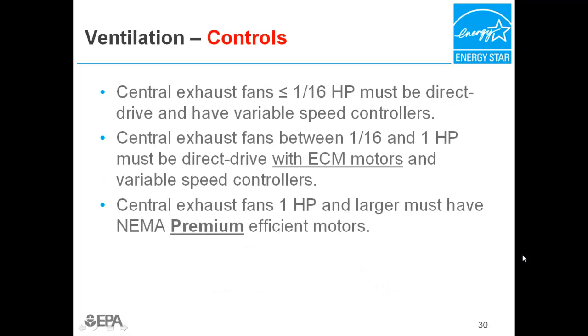All the ventilation control requirements on this slide are only applicable to projects in the prescriptive path. Central exhaust fans 1/16 horsepower and less must be direct drive and have variable speed controllers. Central exhaust fans greater than 1/16 horsepower and less than 1 horsepower must also be direct drive with variable speed controllers, but must also have ECM motors. Central exhaust fans 1 horsepower and larger must simply have NEMA premium efficient motors.